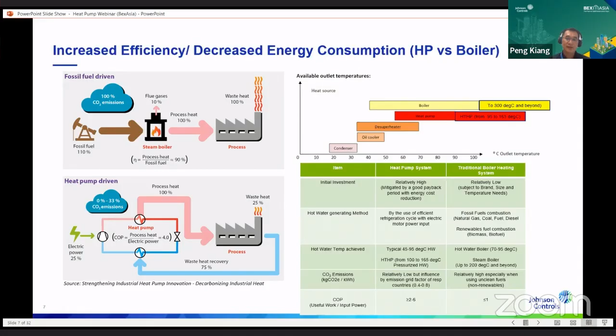In terms of CO2 emissions, it depends on the electricity grid the heat pump draws from—on average a factor of 0.4 to about 0.8 kilogram CO2, depending on the fuel used. A boiler similarly depends on the fuel used. In terms of coefficient of performance, a heat pump is between 2 to 5, or even higher—6 to 7—depending on the temperature lift, whereas a boiler's COP is definitely less than 1. That's one of the major differences.